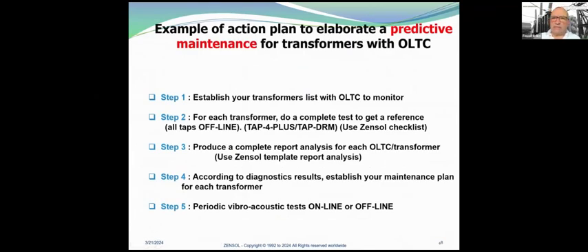Example of an action plan to elaborate predictive maintenance for transformers with OLTC. Step 1, establish your list of transformers with OLTC to monitor. Step 2, for each transformer, do a complete test to get a reference: all taps offline, Tap 4+ and Tap DRM. We have developed a Zensol checklist. Step 3, produce a complete analysis report for each OLTC transformer, and we have developed a Zensol template report analysis, and I can guarantee that at the end of this report, you will understand absolutely how your tap changer is working. Step 4, according to diagnostic results, you can establish your maintenance plan for each transformer, and after you just have to go through a periodic vibroacoustic test, online or offline.